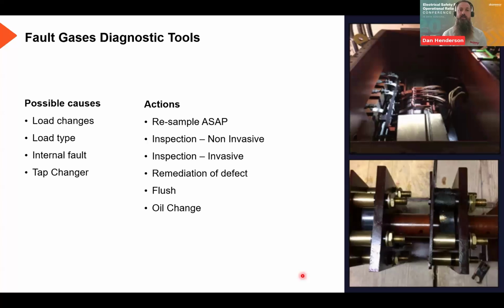It's in a lot of loss prevention and risk management standards. It's definitely in FM Global as a recommendation, and most people adopt that as their insurance method, to conduct DGA as part of regular maintenance. Some of the reasons why this can happen: you can have significant load changes or significant load. If you're overloading your assets, as Ryan's mentioned, that can be a contributor. Then there's the load type. If you've got a large non-linear load, so a lot of variable frequency drives, variable speed drives, or inverters, that can put a lot of non-linear load back into the transformer, which we'll cover in another session next year on power quality and the impacts it has on transformer health.